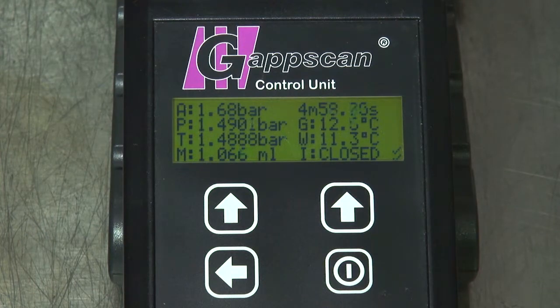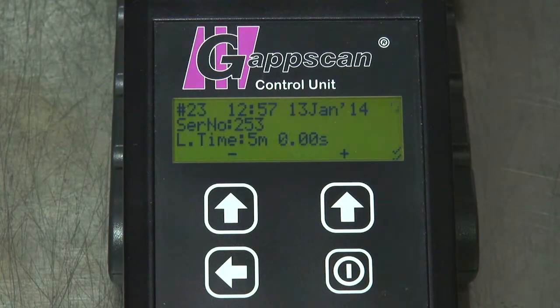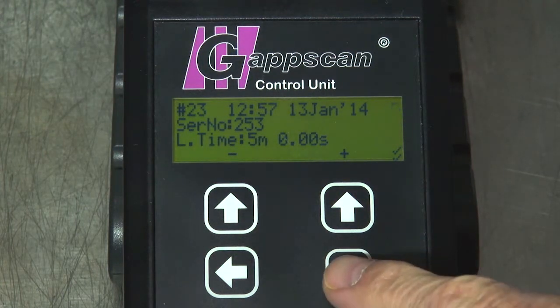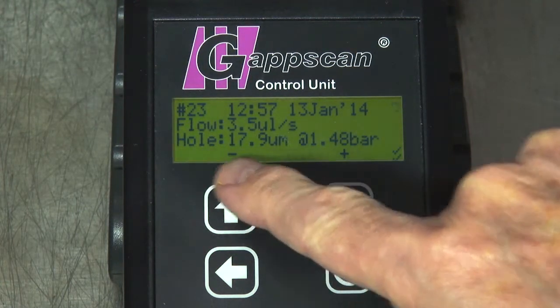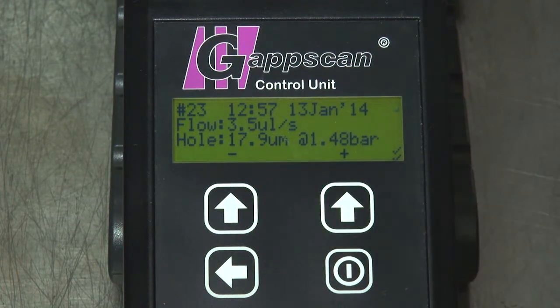When complete, the monitor will switch to the individual test screen shown here. Press the I/O key to display the test data. You can see that the defect size at this lower pressure is 17.9 microns, which suggests several defects.